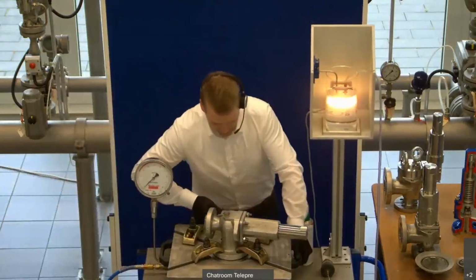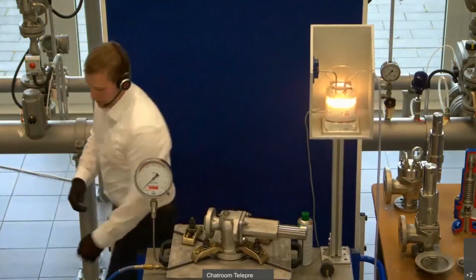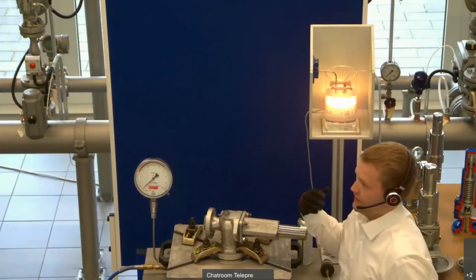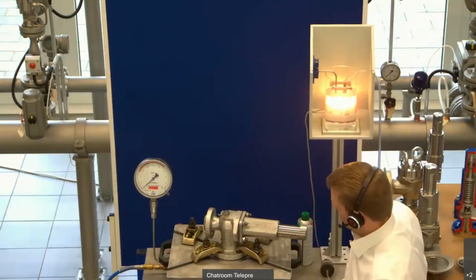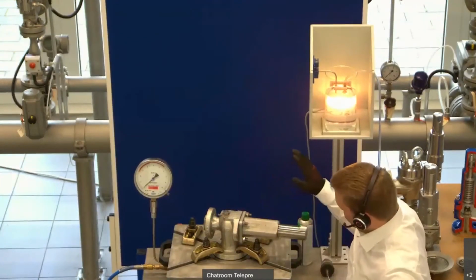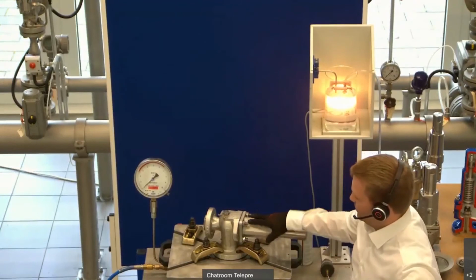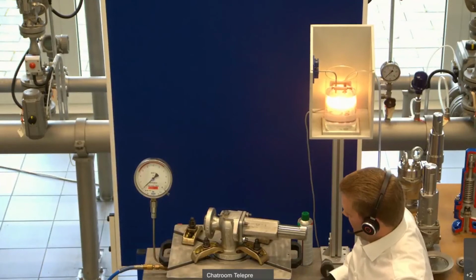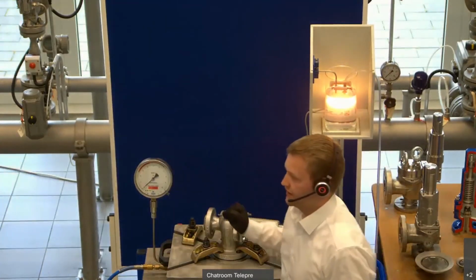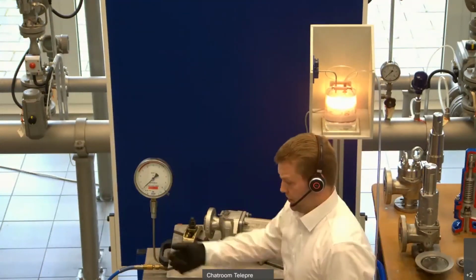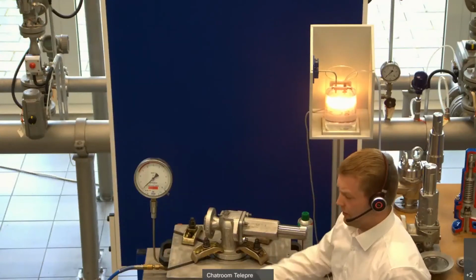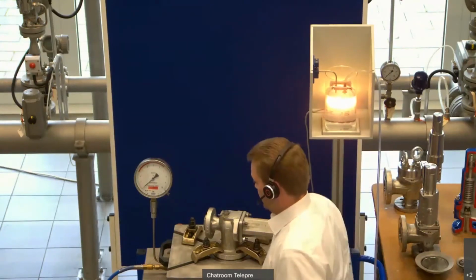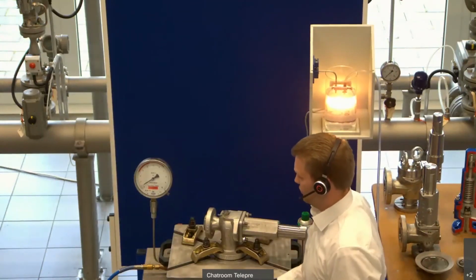Now I've connected, and now we're going to set the test pressure, in this case for the body tightness test. We're going directly to 6 bar G, and keep in mind I don't reach 6 bar G because I'm using the control air from the Leser chat room. It's going to about 5.5 bar G. But for the test, it is important to go to 6 bar G.